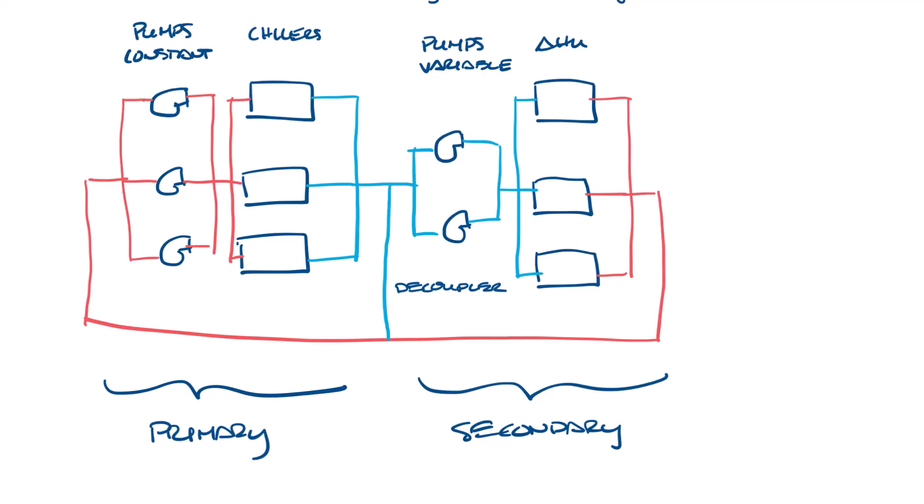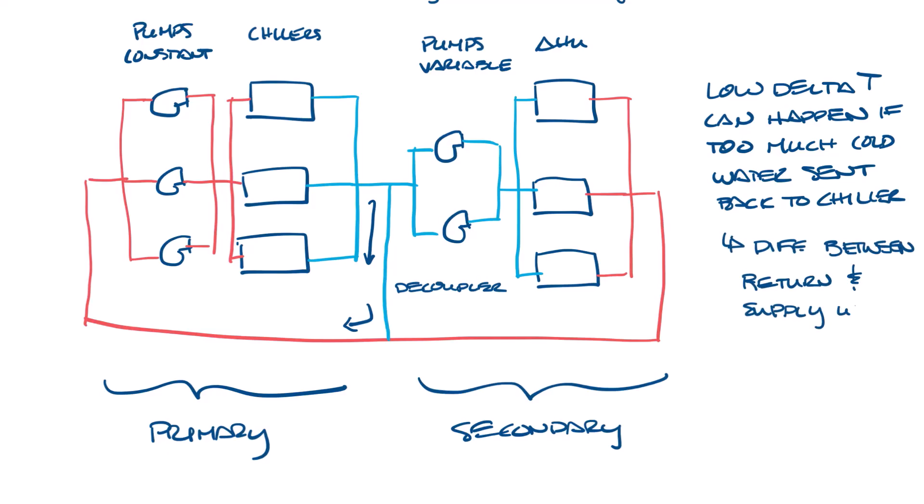When the secondary pumps are running slower than the primary, water will be diverted through the decoupler to balance the system. This can cause low delta T issues if too much cold water is sent back to the chillers. I'll cover low delta T syndrome in more detail in another video. But as the name implies, it's when the difference in the supply and return temperature is too low.